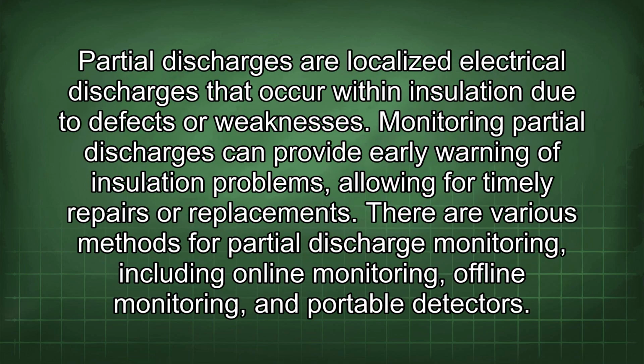Partial discharges are localized electrical discharges that occur within insulation due to defects or weaknesses. Monitoring partial discharges can provide early warning of insulation problems, allowing for timely repairs or replacements. There are various methods for partial discharge monitoring, including online monitoring, offline monitoring, and portable detectors.